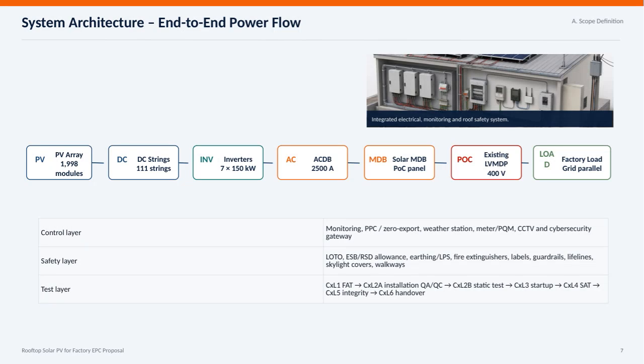Here we have a comprehensive overview of the system architecture for the rooftop solar PV installation proposed for the factory EPC project. The system starts with a large PV array comprising 1,998 modules organized into 111 DC strings. These strings feed into 7 inverters, each rated at 150 kilowatts, converting the direct current to alternating current. From there, the power flows through a 2,500 amp AC distribution board and then a solar main distribution board, which integrates with the existing low-voltage main distribution panel operating at 400 volts. This setup supports the factory load while operating in parallel with the grid.